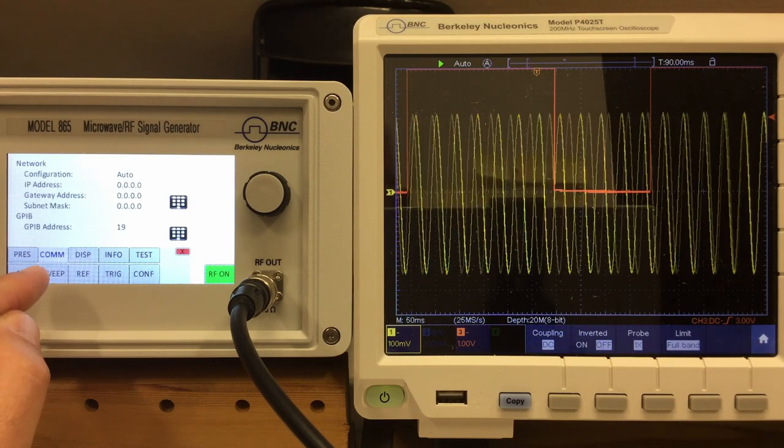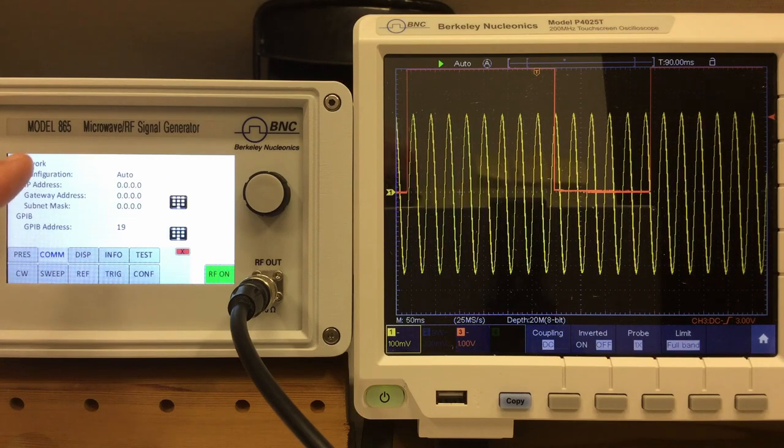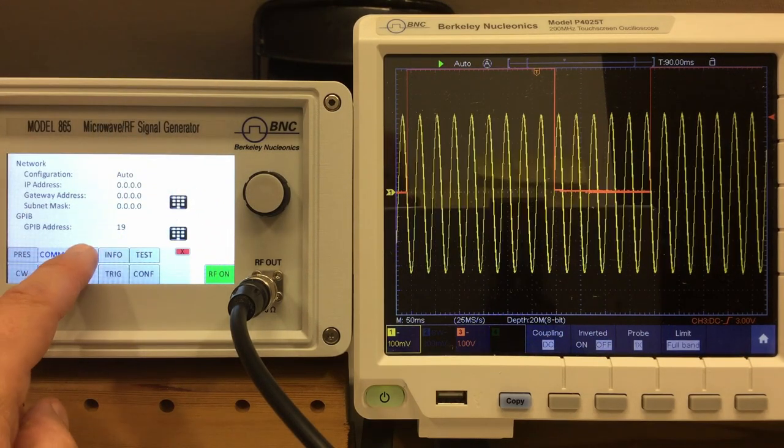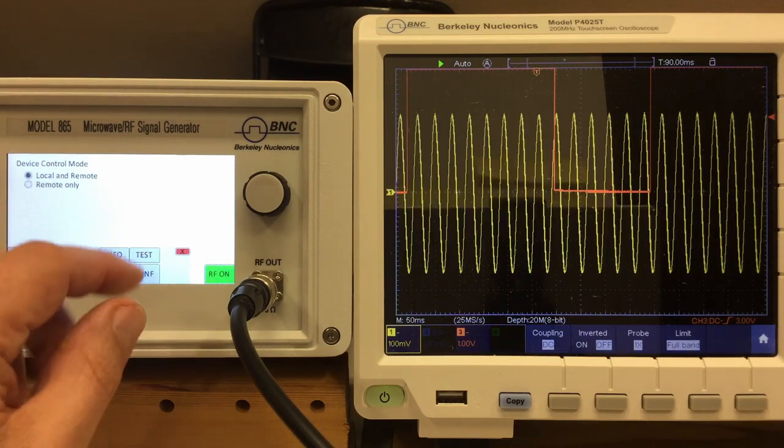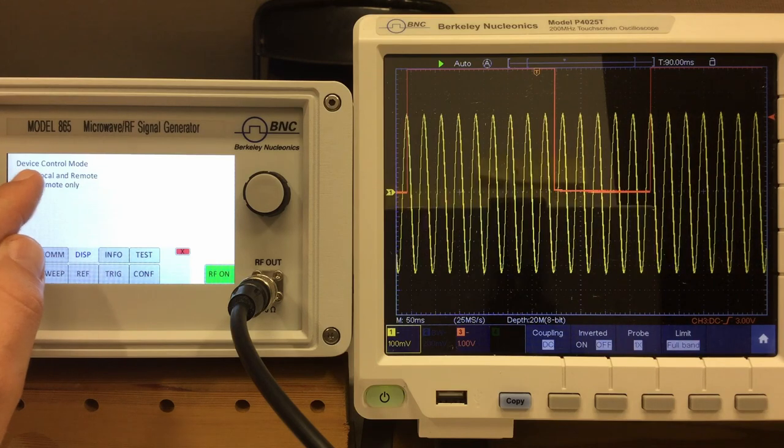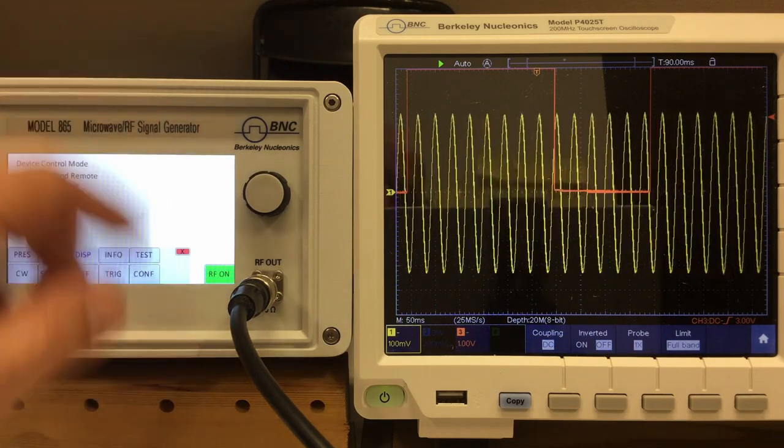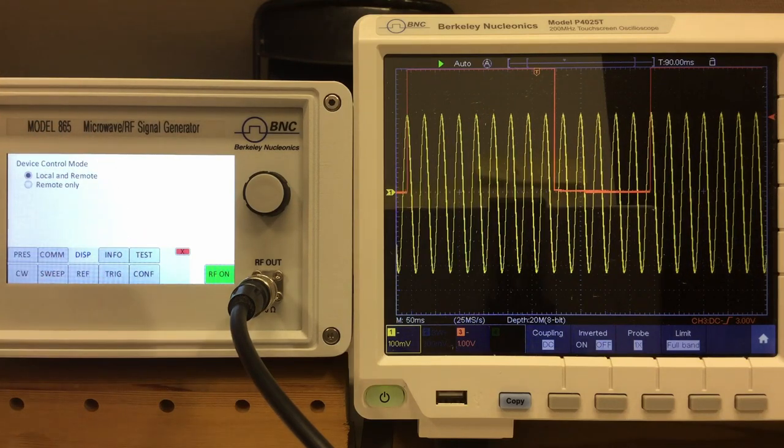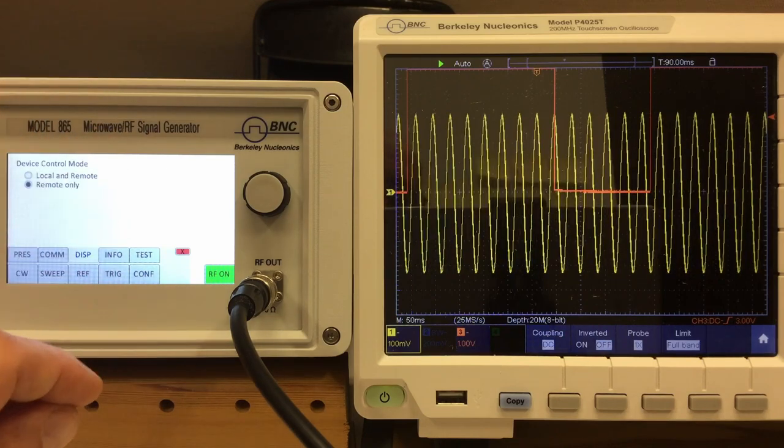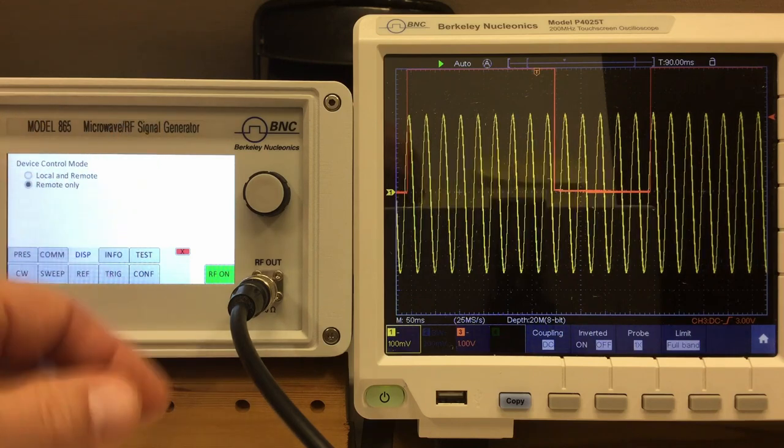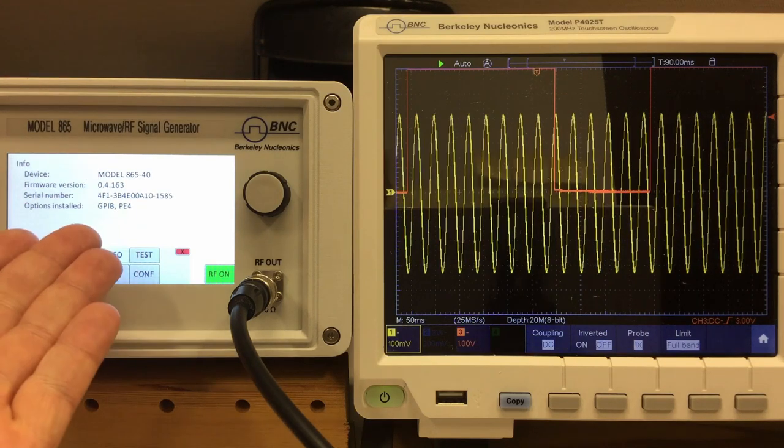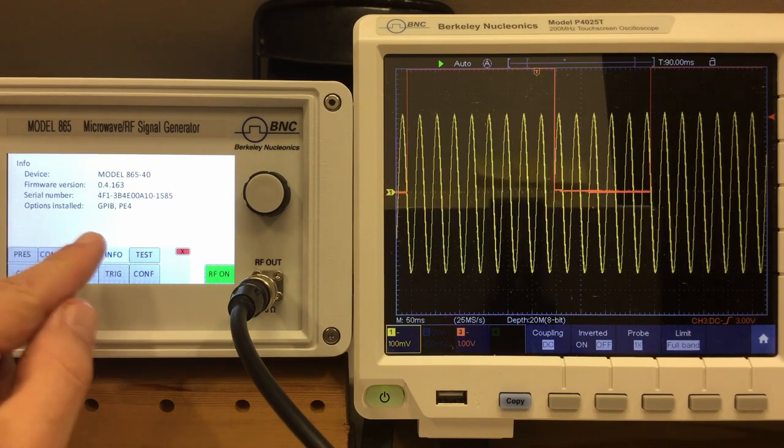We won't talk today about the communications menu. That's the network LAN communication and the GPIB address communication. That's for the second part using that unit remotely. Display is just a little fail-safe. So you can set your device control mode between local and remote. So I can use the touchscreen and control the thing via LAN or USB or GPIB, or I can say remote only. So nobody in the lab when this is centrally controlled will mess things up. Okay, let's leave that at local and remote for now.